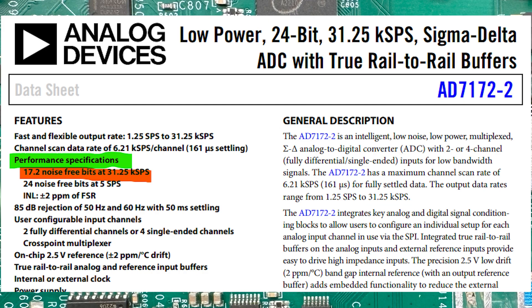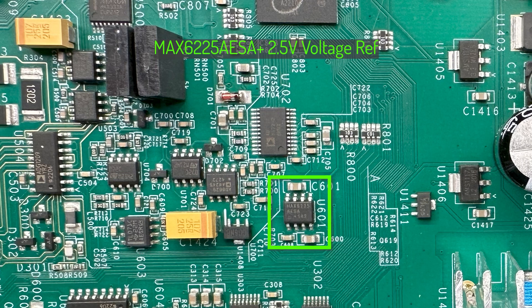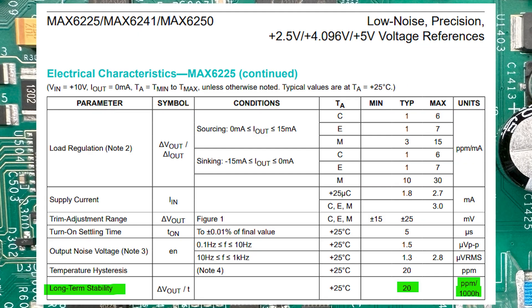The AD7172-2 does have an internal 2.5V voltage reference, but I don't think they're using that one because we have the MAX6225AESA+, which is a 2.5V voltage reference with a typical tempco of 1.5ppm per degree Celsius, and the long-term stability is quoted as 20ppm per thousand hours at 25°C. Many people were interested in this, so now you know it uses a pretty good and stable voltage reference, which is adequate for this class of instrument.